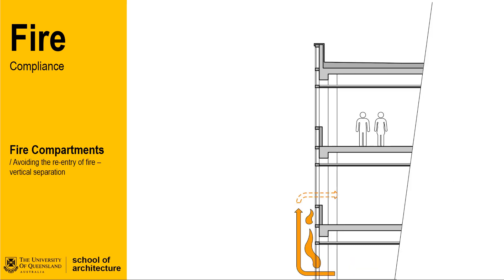There are two strategies for preventing a fire leapfrogging up a building. The first is through vertical separation, where the provision of a fire-rated spandrel behind the curtain wall on the floor above can slow the rate of fire spread up a building. Vertical separation is typically the only way to prevent the spread of fire up a building that uses a curtain wall strategy. The second strategy is to provide horizontal separation, where a horizontal barrier is provided between levels, usually as a slab extension. The projection width is a deemed-to-comply solution described in the NCC and is dependent on the building class. This solution is more applicable to window wall facade strategies.